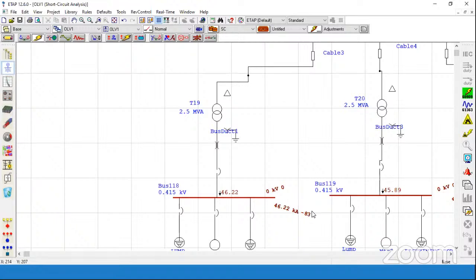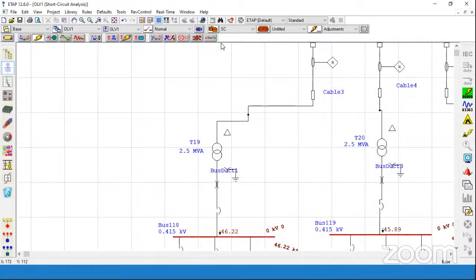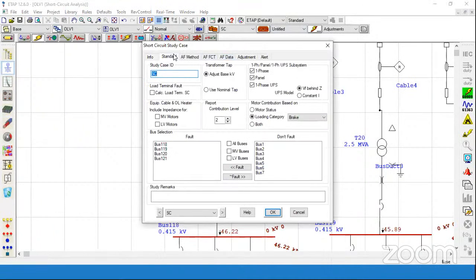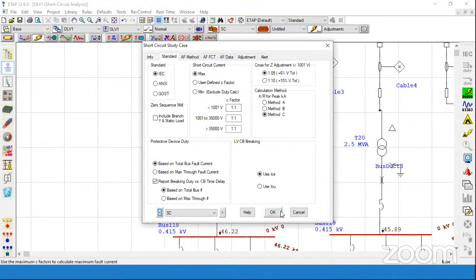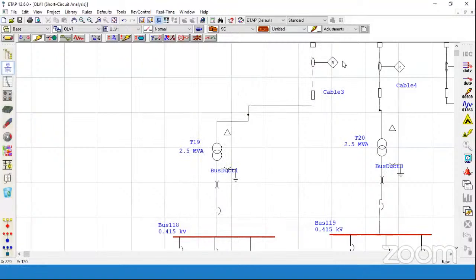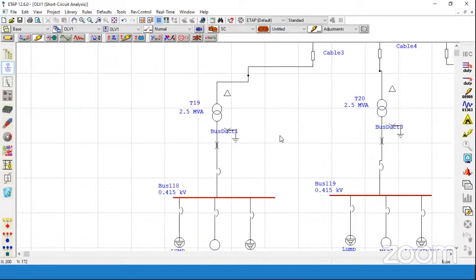So relay coordination is done based on the minimum and maximum fault current conditions, and accordingly we need to calculate the settings for this particular fault current. I will go for the maximum fault current condition, such that for maximum, it will automatically calculate for minimum also. Now let's go with here.